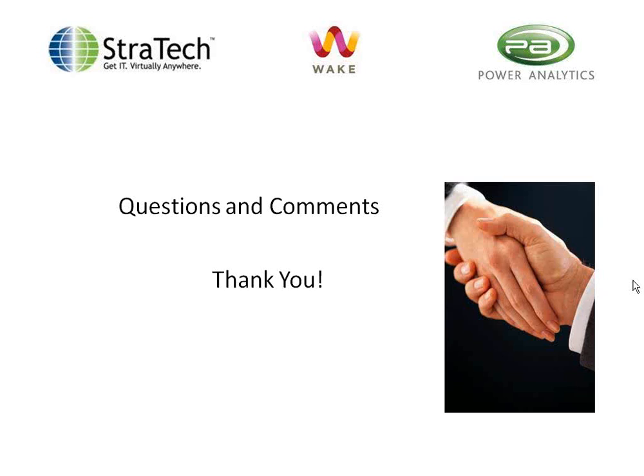This is Chris again. The load flow tool I mentioned earlier is fed with live data from the network. Loads are read in real time through the PI historian, and that data is loaded in real time into the load flow software, which calculates based on current real-time information on the system. The Blackboard takes a copy of that and allows changes to be made, using real-time information, but you can change the system configuration or scale loads, then calculate a simulation of what would happen with those changes using real-time data. So you can make configuration changes and compare what's really going on in your system to what could be going on.